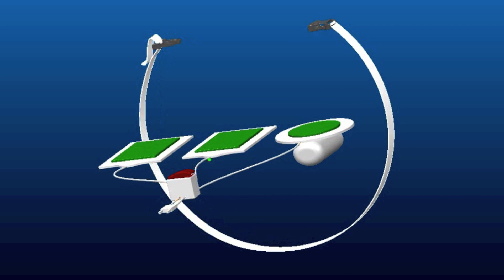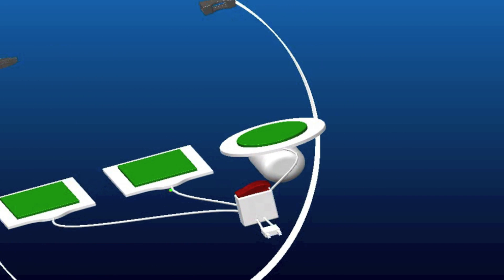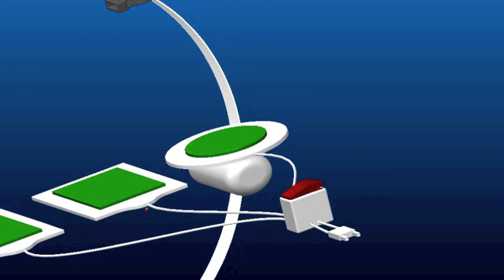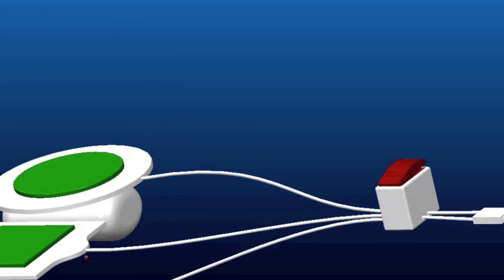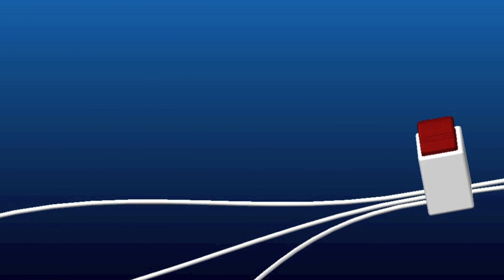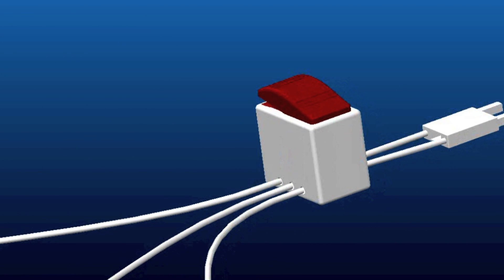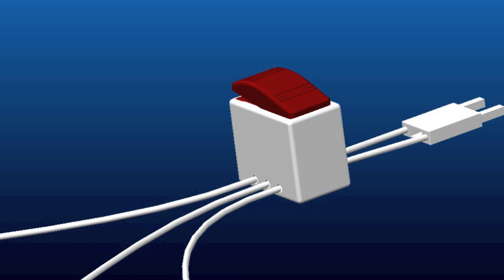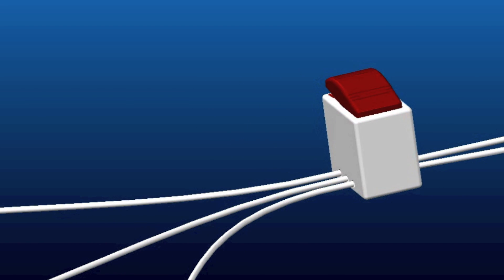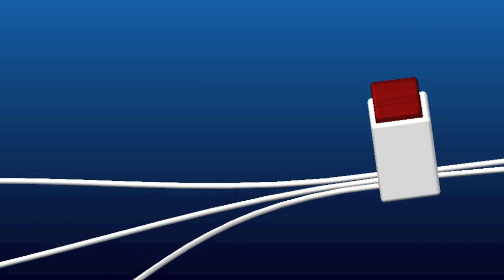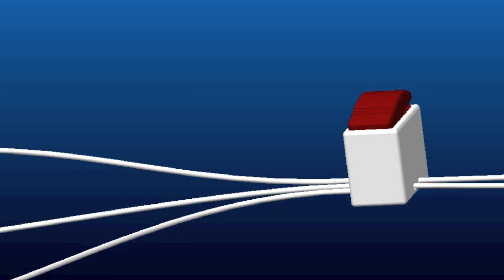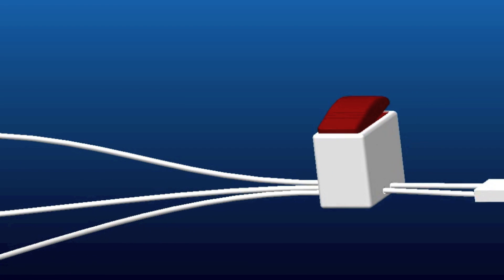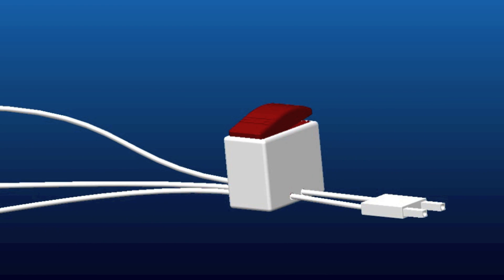Switching the shock vector can be done by changing the patch locations. Current patches cannot be relocated because they lose their adhesiveness, which is crucial to how effective they are. The Presto Patch uses a novel 3-patch design, which makes relocation of patches unnecessary. With just the press of a button, the doctor can choose which two patches to send the current through.